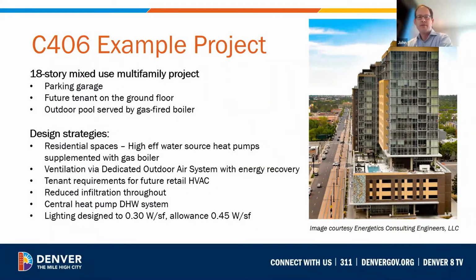Some of the design strategies used for this project are high efficiency HVAC equipment. They decided to use water source heat pumps that are supplemented with a gas boiler for backup. They're using a dedicated outside air system with energy recovery for ventilation, reduced infiltration throughout the building, and a central heat pump domestic hot water system for water heating. The building also has efficient lighting, designed so that the overall lighting for the entire building has a lighting level of 0.3 watts per square foot. That compares with the code allowance of 0.5 watts per square foot. So we're going to simply show how this project would size up using the energy credit tool in the prescriptive planning.